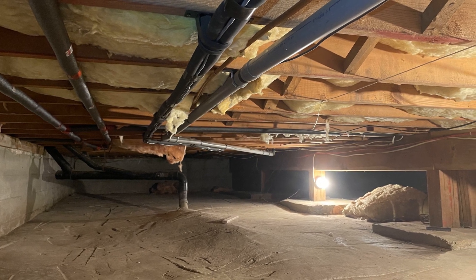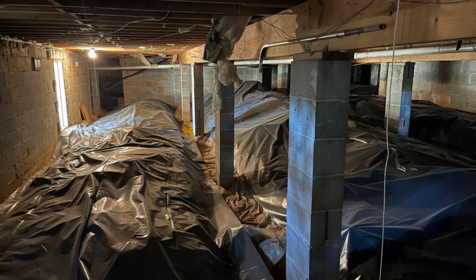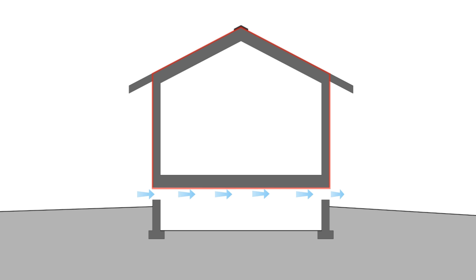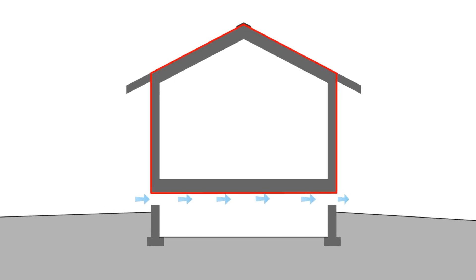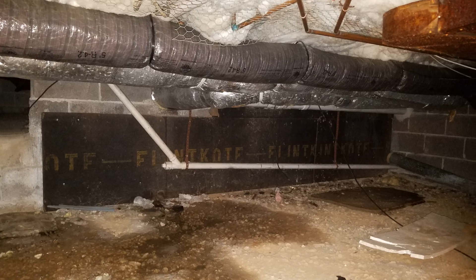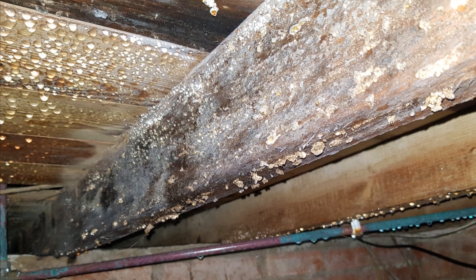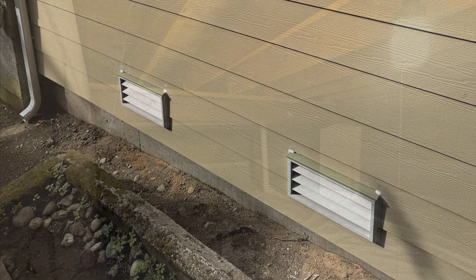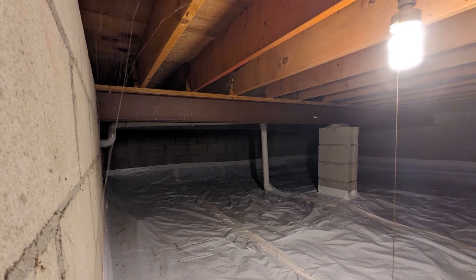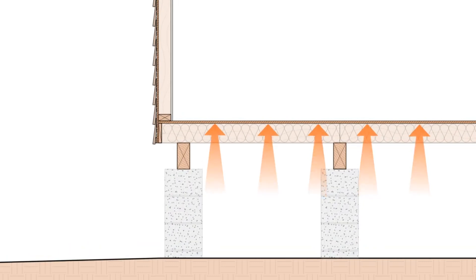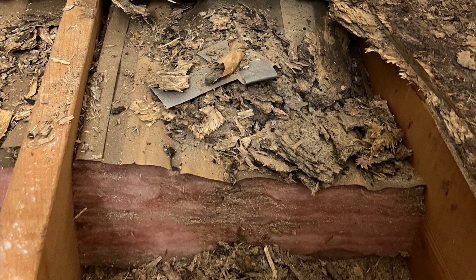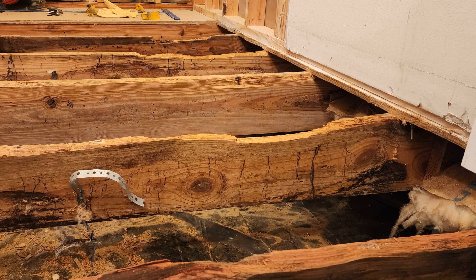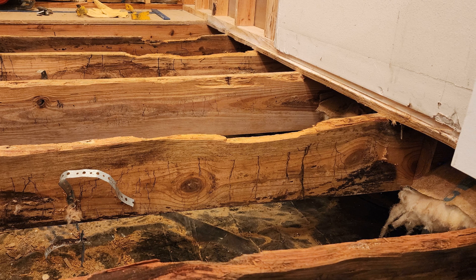Our last location where we tend to see a lot of problems is in crawl spaces, particularly in semi-vented or ventilated crawl spaces. The problem with crawl spaces that are not located within the conditioned space is that we get a bunch of air from the exterior migrating into this interstitial space where we have no control over the environmental conditions, and that outside air can often bring with it humidity. That warm, humid air from the outside migrates to the inside of the crawl space — especially if we're readily letting it in through crawl space vents — and it's cooler inside, especially if we're air conditioning the interior space. That warm, moisture-laden air tends to condense on the underside of the subfloor, causing a ton of rot and mold in the floor structure.